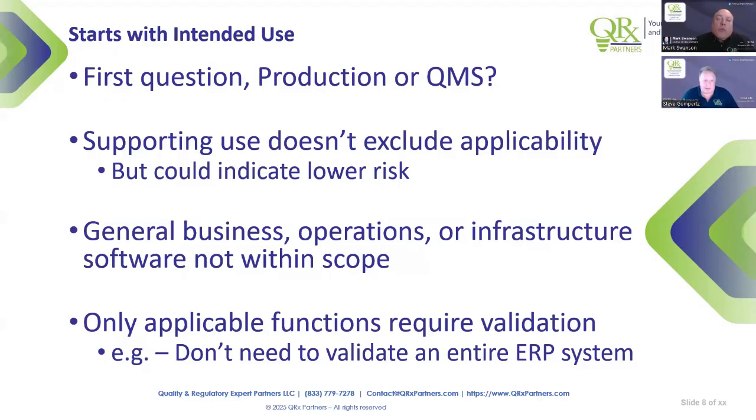But other stuff, you're going, well, it maintains our ID and traceability capabilities. Okay, well, that's a regulatory requirement. That part of the ERP is going to require some degree of validation, right? But other aspects of it, like the cost of the part, is not part of your quality management system. If you're doing costing analysis, that doesn't apply. So again, you do get to scale it, because I know that question has come up and people are just going, "Oh man, how do I validate all of SAP?" You're not required to, and this gives you that guidance on how to make those decisions.